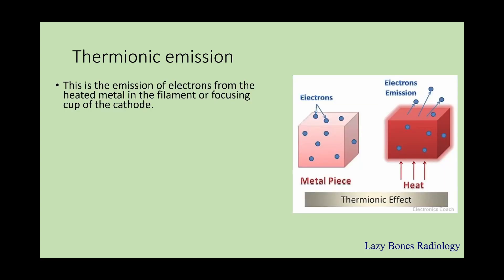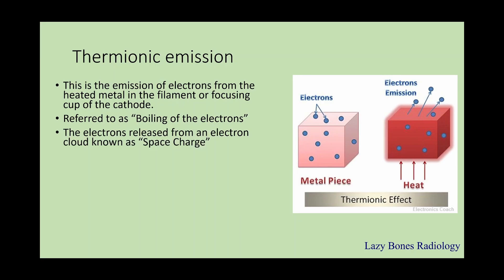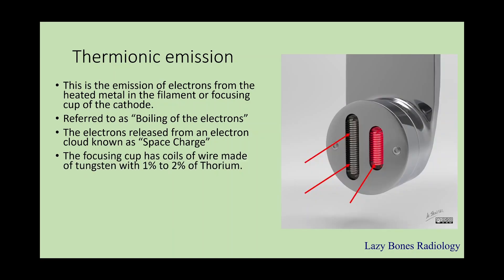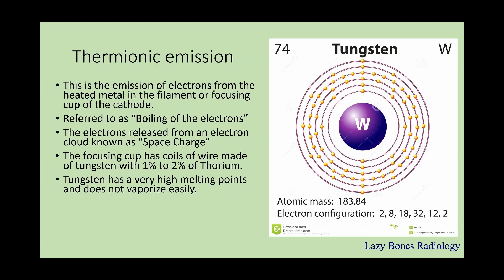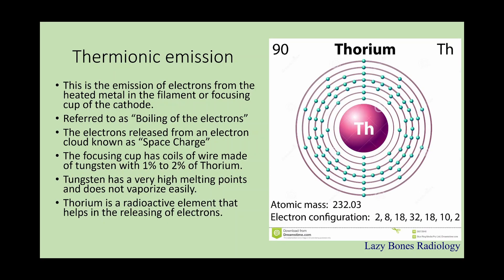Now let's begin with the x-ray production. First we start with thermionic emission. This is the emission of electrons from the heated metal within the filament or the focusing cup inside of the cathode. This is referred to as boiling of the electrons. As the electrons are boiled off, they form an electron cloud, which is known as a space charge. The filament coils are made out of tungsten and one to two percent thorium. The reason we use tungsten is because it has a very high melting point and does not vaporize easily, and the reason we use thorium is because it's a radioactive element that helps release electrons.